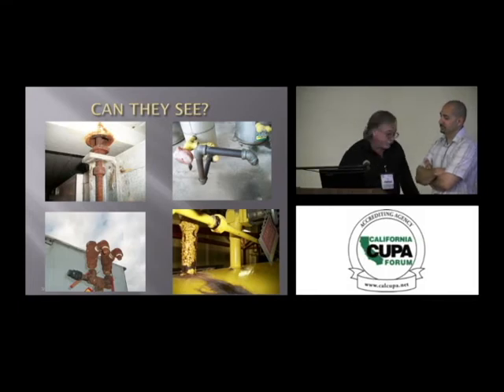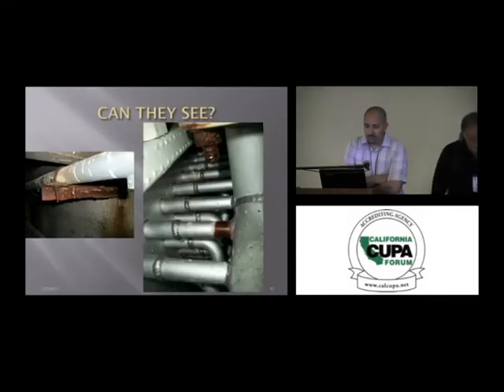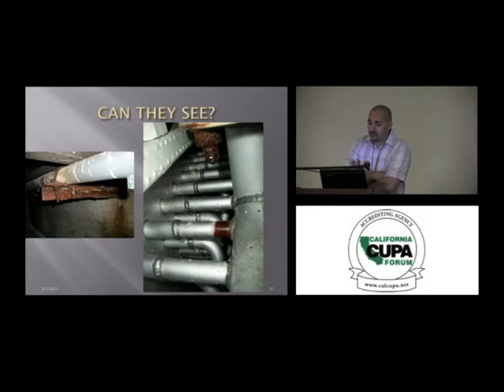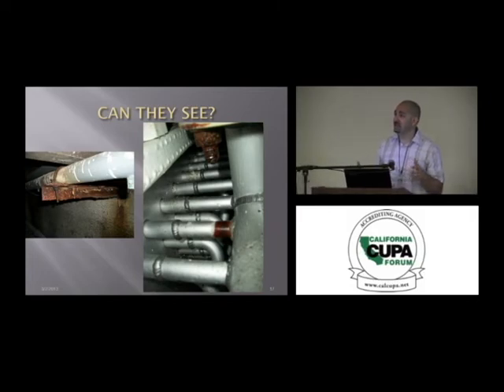Go ahead. More corrosion going on here. Again, this is inside of a bunker. A bunker is, I'm sure, the least visited area of an ammonia system. We get in there and find a lot of the corrosion falling off of supports.